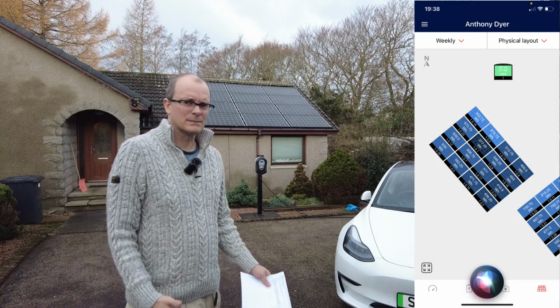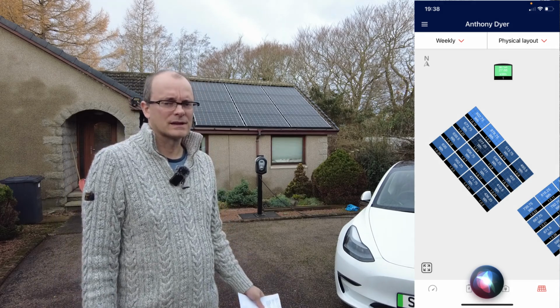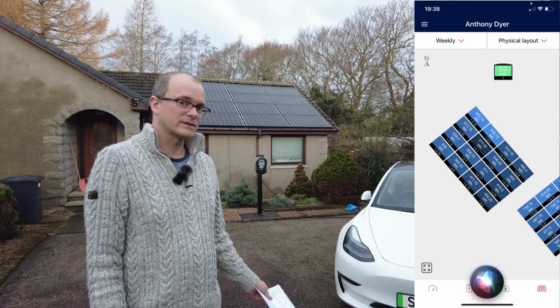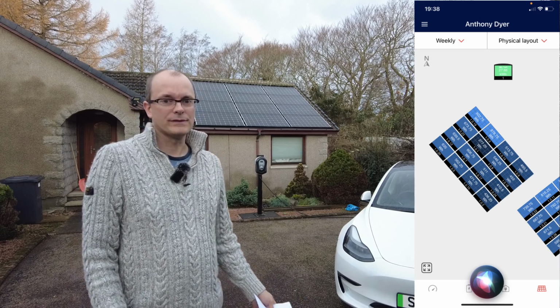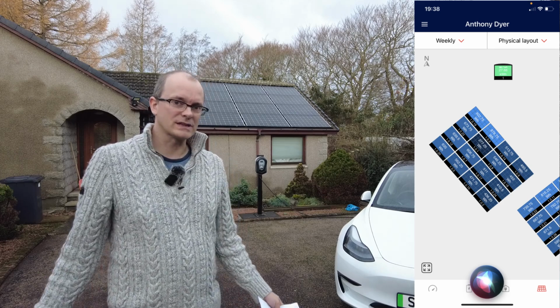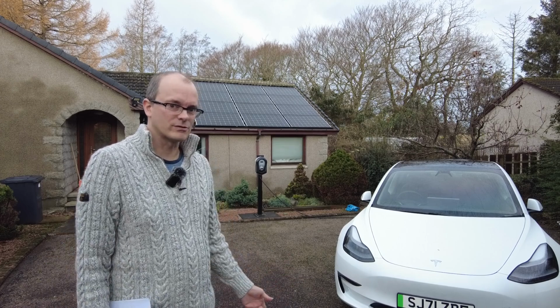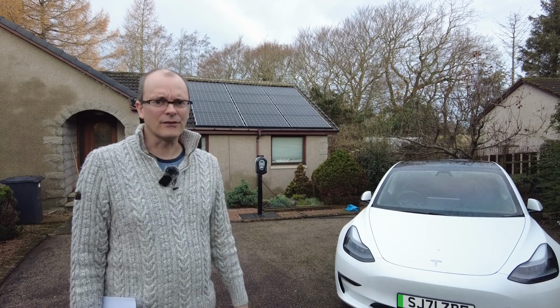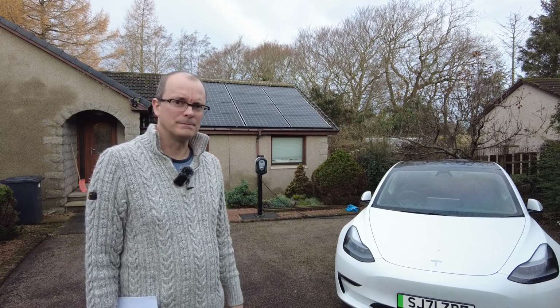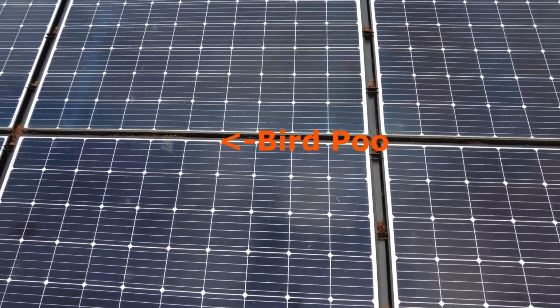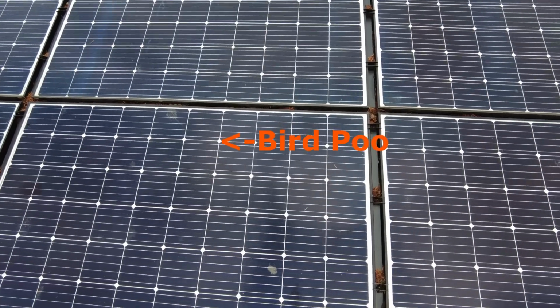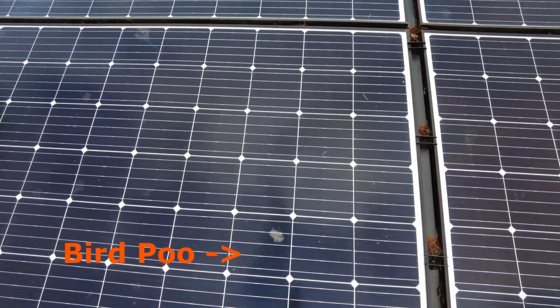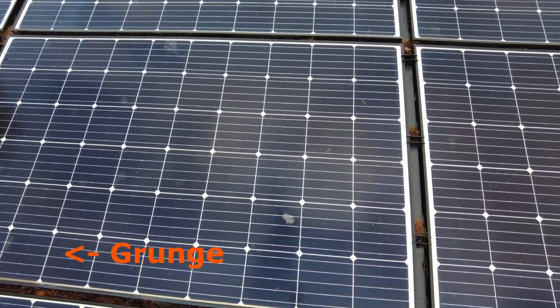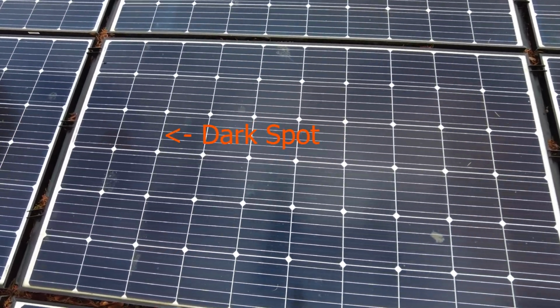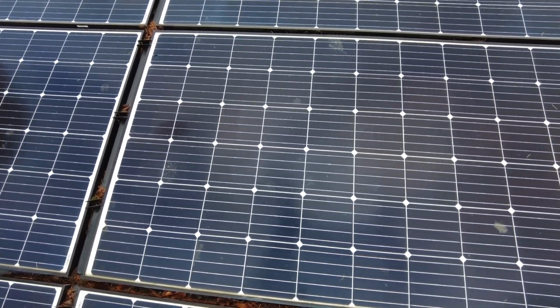Now, this can be due to a variety of factors, one of which is obstruction of the solar panel. So if it's dirty, or if you've got leaves or bird poo obstructing the solar cells, you can find that the output of the solar panel can be reduced dramatically. So what we're going to do is have a look at this solar panel in a bit more detail. So what I'm looking for here are defects to the solar panel. I'm not looking for obstructions. I can see that there are no obvious obstructions from the ground, but you can't see defects obviously.